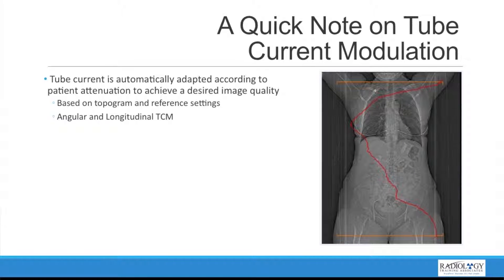I want to take a side step here and talk about tube current modulation because this will become important later when we discuss the impacts that CT shields have in our departments. Tube current modulation is a way for a CT scanner to automatically adapt the mAs according to the patient attenuation seen in the topogram and the desired image quality. The topogram and the image quality reference settings tell the CT scanner how much the mAs should go up or down — this can happen angularly as the x-ray tube rotates around the patient, and longitudinally as the patient moves into the scanner in the z-axis.